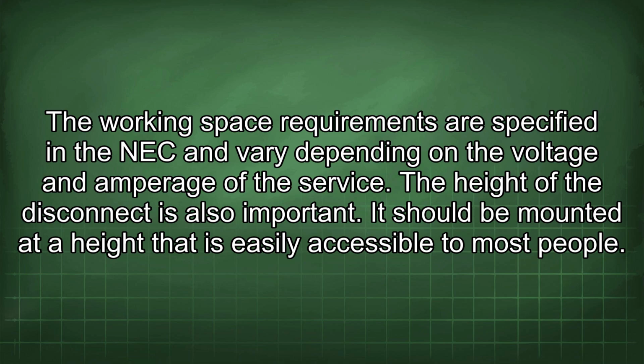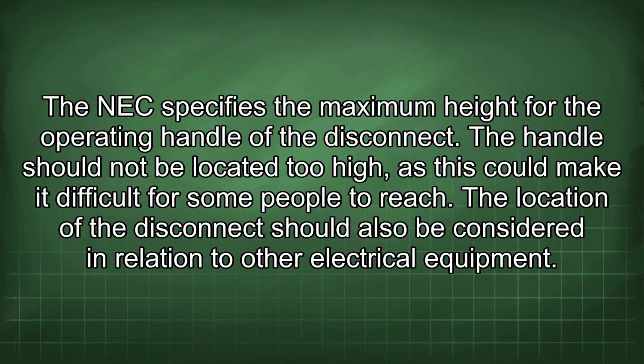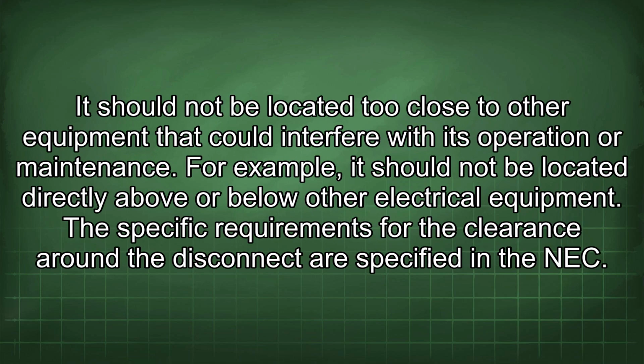It should be mounted at a height that is easily accessible to most people. The NEC specifies the maximum height for the operating handle of the disconnect. The handle should not be located too high, as this could make it difficult for some people to reach. The location of the disconnect should also be considered in relation to other electrical equipment. It should not be located too close to other equipment that could interfere with its operation or maintenance. For example, it should not be located directly above or below other electrical equipment. The specific requirements for the clearance around the disconnect are specified in the NEC.